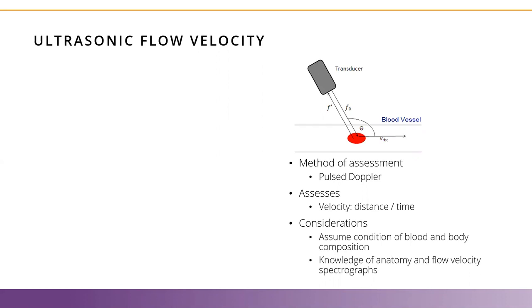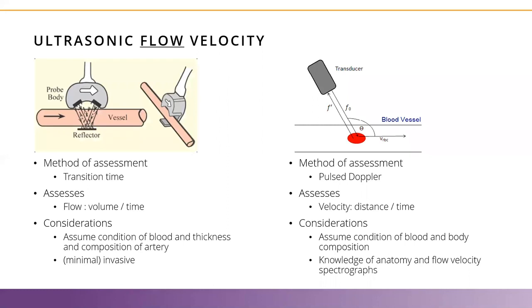But there is also another option to use ultrasound to do a flow measurement. Here it is being depicted, and you can see that it's basically using ultrasound, a reflection on a solid surface, as indicated here, and being captured, and a second beam being sent back, reflected and being captured. By measuring the transition time, you will be able to calculate a flow through this measurement area. With this technology, you're able to do a flow measurement in milliliters per minute, for instance, in units. However, this technique has to be done in an invasive, or at least a minimally invasive manner, where you basically hook the artery of interest and then do your flow velocity measurement.